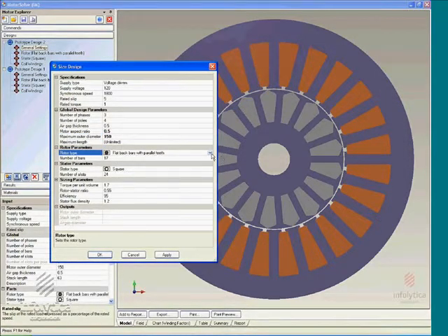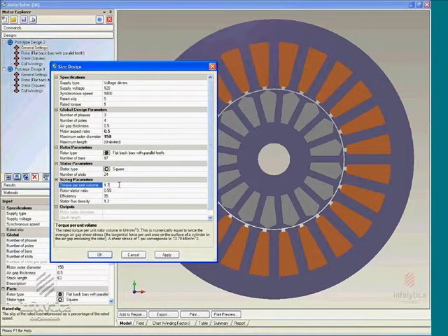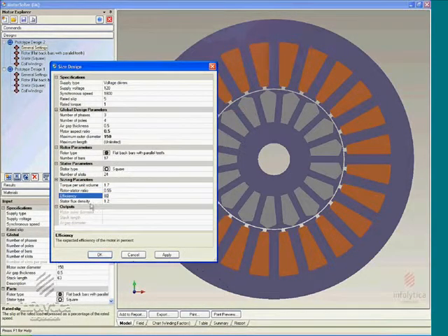The rotor types can be specified, as well as the number of bars, stator geometry, and number of slots, which brings us to the main parameters that determine the outcome of the sizing algorithm: the torque per unit volume and the rotor stator ratio, some typical values of which are reported at the bottom for any given field. So 50% for two poles, 55%, the default value, for four poles, etc. Efficiency can also be specified, as well as flux density and so forth.